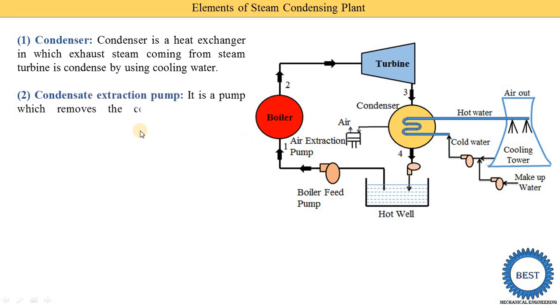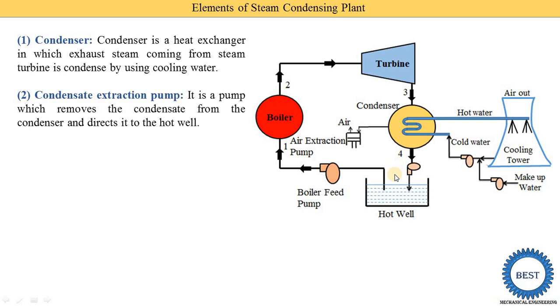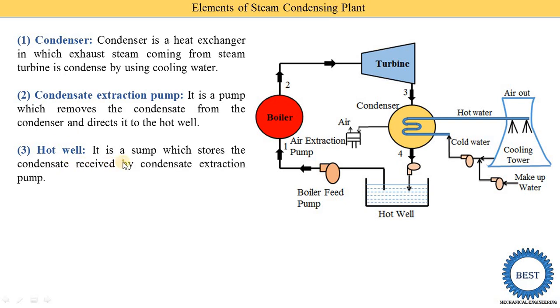The second component is the condensate extraction pump. During the cooling process, the steam is converted into water and this water is collected into the condenser. This condensate water is supplied to the hot well by using the condensate extraction pump. The third component is the hot well — it is a sump which stores the condensate received from the condensate extraction pump.